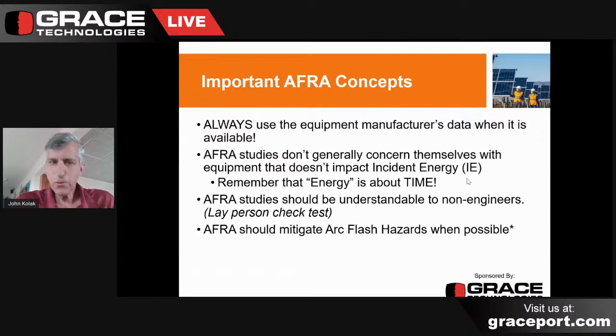The second point is also quite important. Arc flash studies don't generally concern themselves with equipment that doesn't impact incident energy. And why I say that is that, for example, we don't normally model things like solid blade disconnects and things like that in the system, because if it doesn't impact incident energy, they don't spend much time modeling that process. So you'll notice when you look at some of the models I'll show you, they're obviously absent things like disconnects, or in some cases circuit breakers that don't have an impact on incident energy calculations.